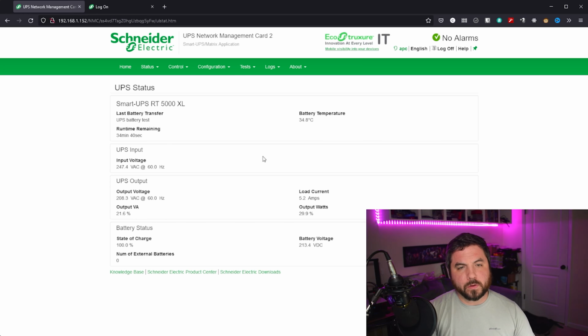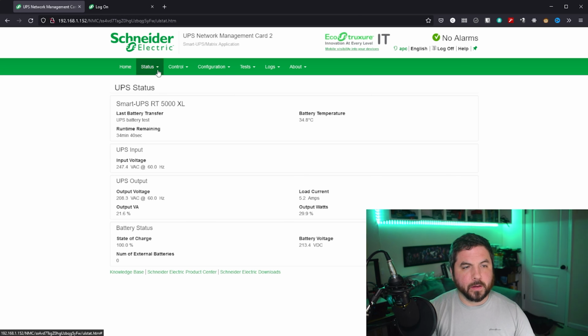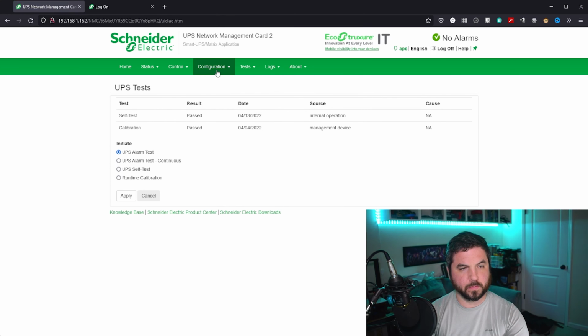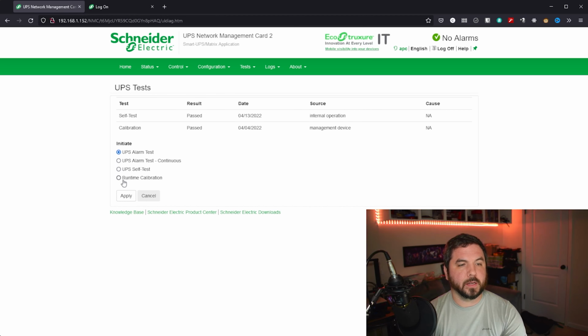And once you are into the management system, you may see that your runtime remaining, especially if they're brand new batteries, is seconds. And don't be alarmed by that. That just means that you need to do some tests. Don't be alarmed by low battery remaining. That just means you have to do some tests. And I recommend running this runtime calibration test or equivalent several times, 3, maybe 4 times. The more times that you run this, the better your calibration will be on the battery, and the better the runtime remaining estimation will be.